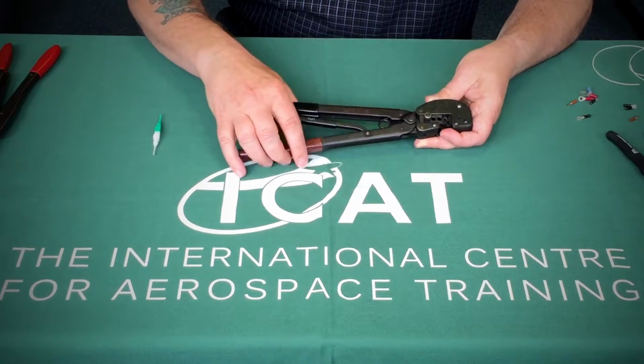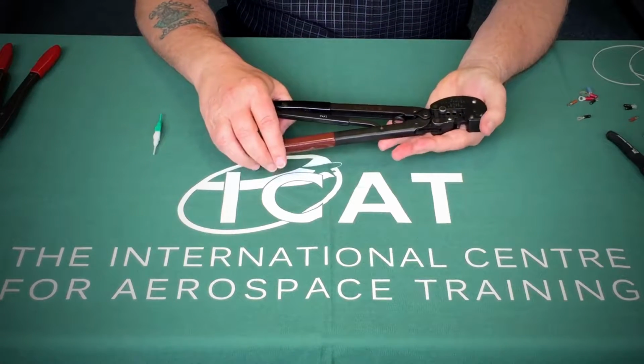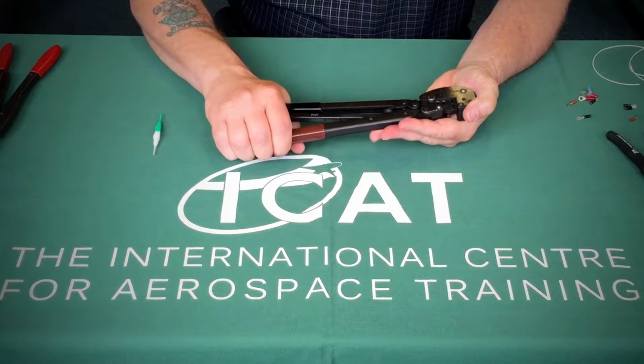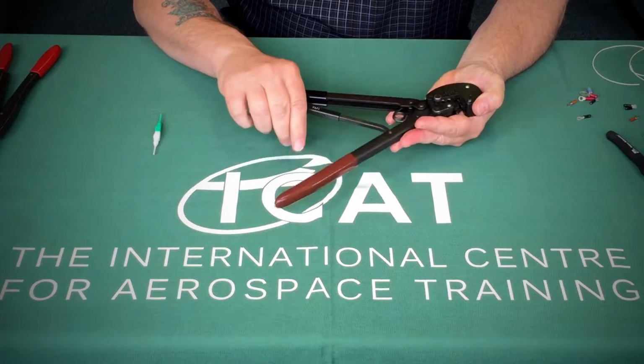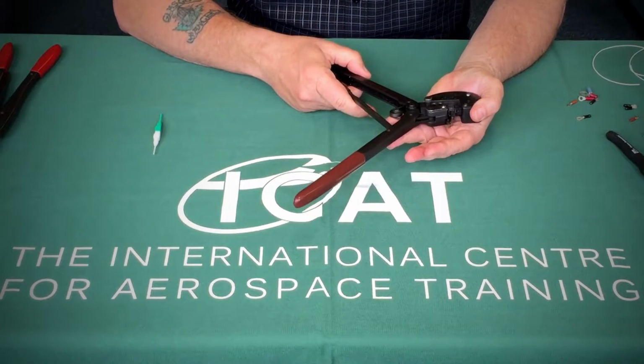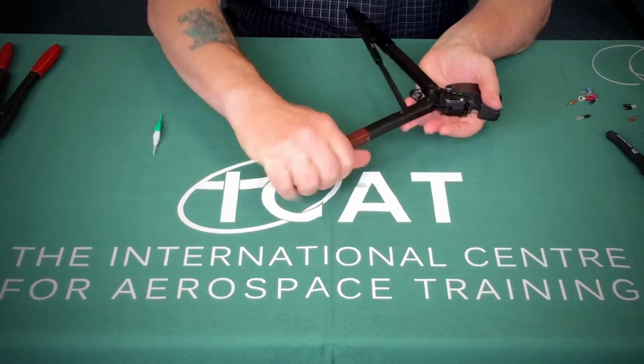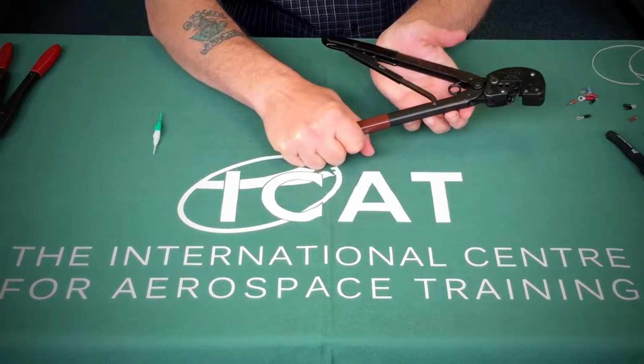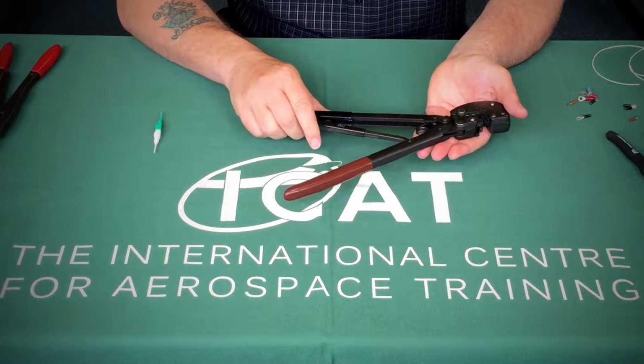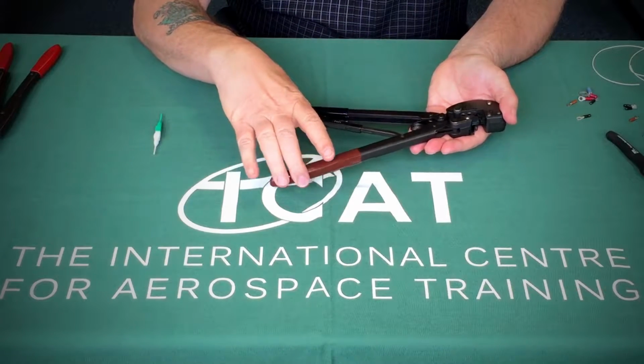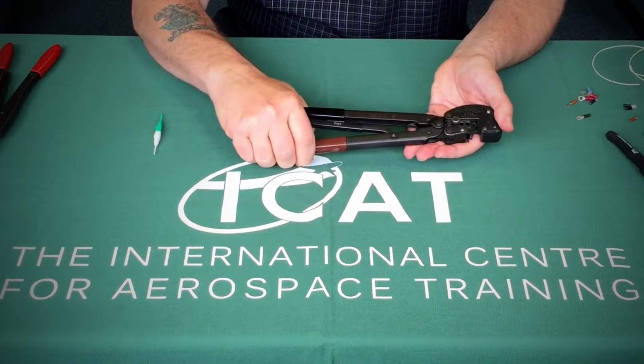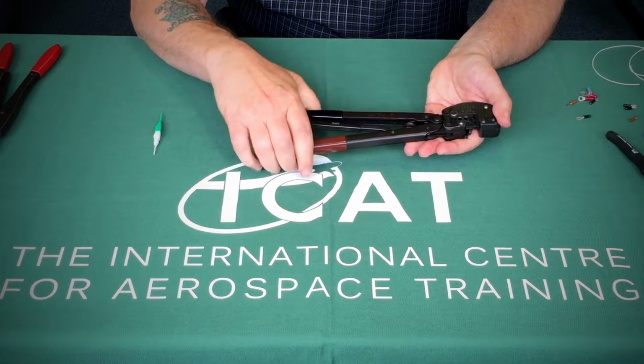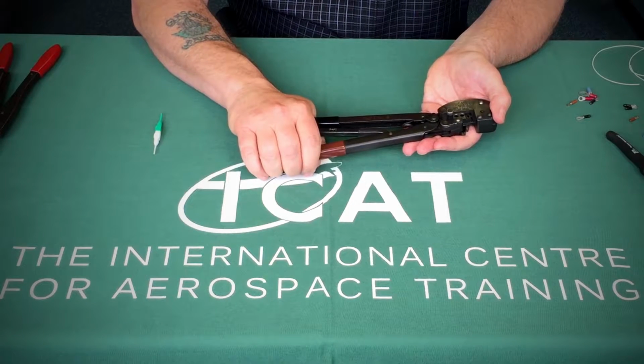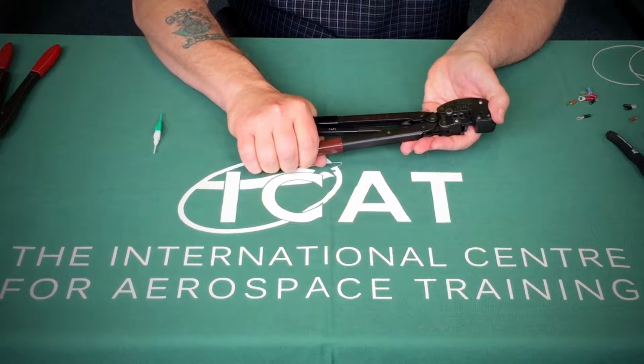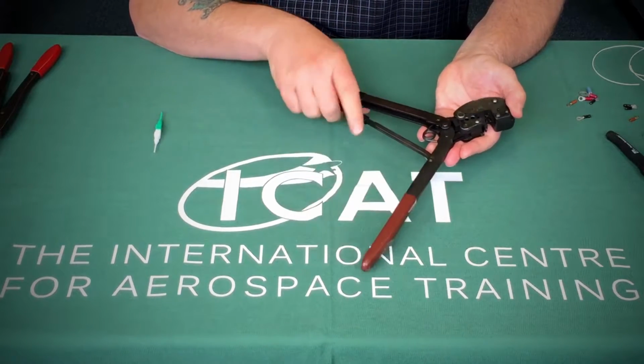As with all crimp tools, they work on a ratchet mechanism. To fully open the tool, you depress the handles and it will open fully. Once you start the crimp tool, it is a ratchet mechanism, and the only way to release it is to fully close the crimp tool itself. So be very careful, make sure the crimp is correctly located before you close the handles completely.